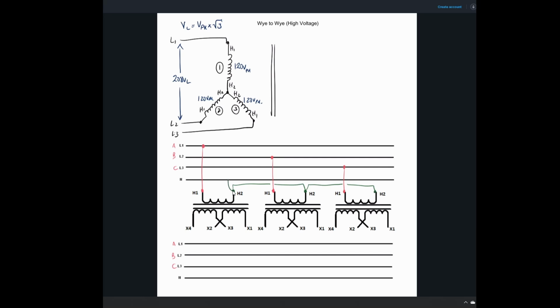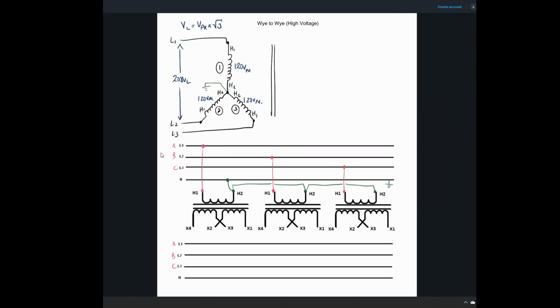And on this diagram, I'm going to bring that up to this neutral, and that guy is going to be bonded to ground. But just keep in mind that in our shop, we don't actually have a neutral on our feed. So you're just going to jumper all your H2s together there. Everything stays the same in that the voltage on the phase, if we have 208 3-phase coming in, means that our voltages here are identical to the previous diagram. And that gives us 120 volts on the phase. So you can see up above on this diagram, we still have the 120 volts there.